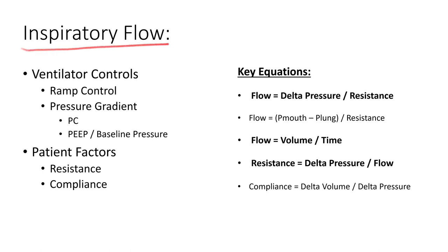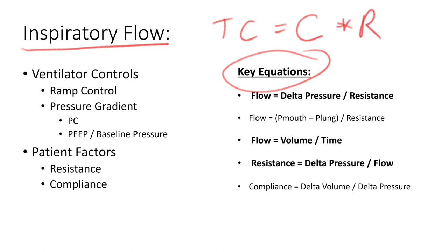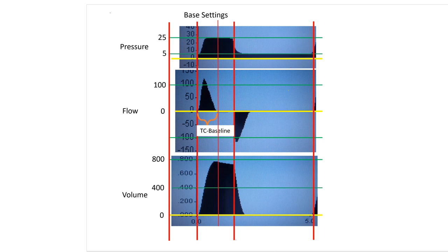In this short video, I'm going to demonstrate some of the factors that affect inspiratory flow and the time constant. Keep in mind the key equation: time constant equals compliance times resistance. We're going to look at how changing ventilator controls — such as the ramp control and the pressure gradient — as well as patient factors like resistance and compliance, affect inspiratory flow and time constant. We'll be looking at our pressure, flow, and volume waveforms for this analysis.